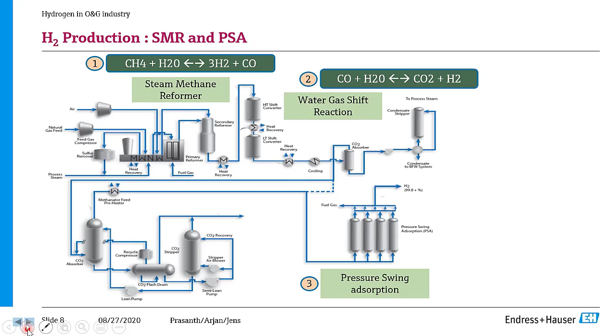In terms of portfolio from Endress+Hauser, we offer a complete portfolio for SMR and PSA processes. What you see on the left top, where my cursor is, is steam and natural gas flow. The Vortex flow meter is a globally accepted flow meter for steam flow measurement, and on the right side is our process ultrasonic flow meter for natural gas flow measurement.